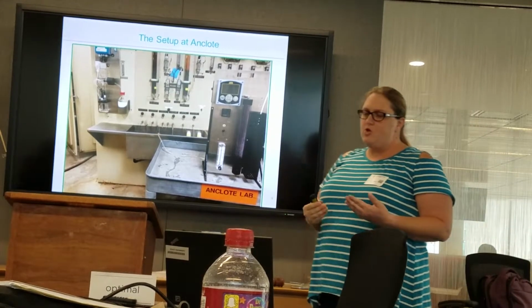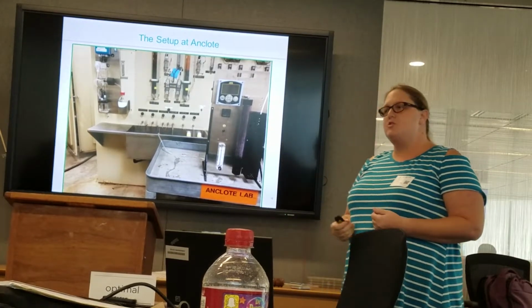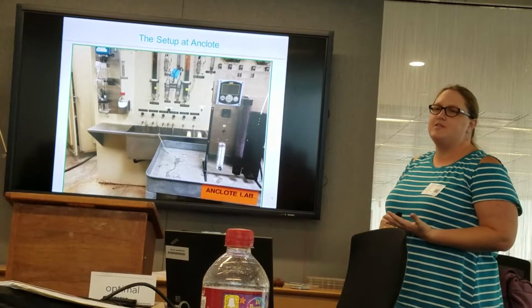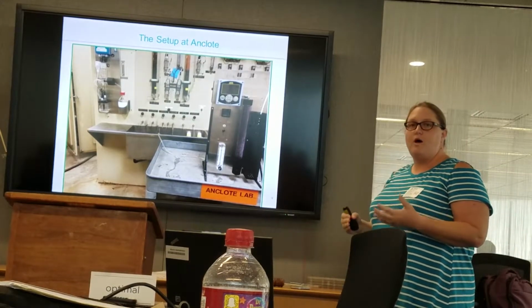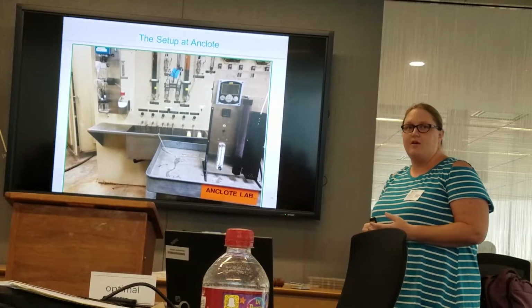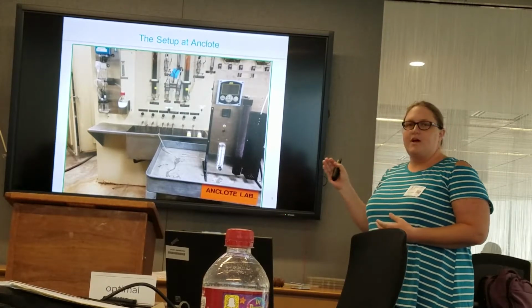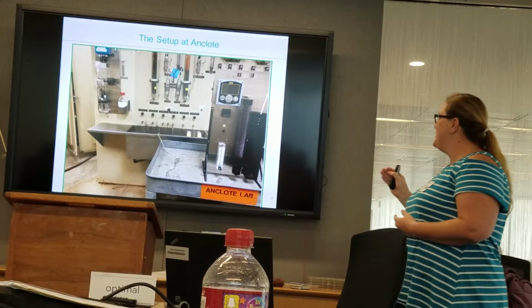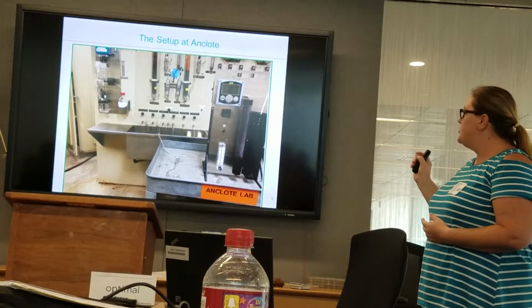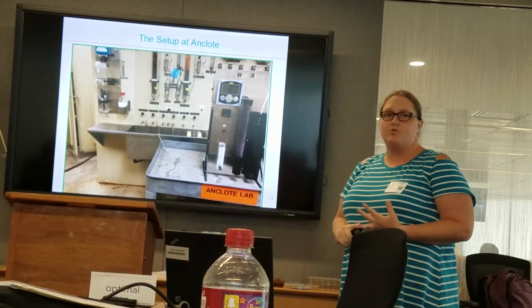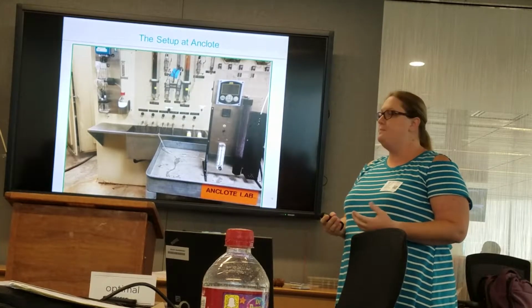So the way Anclote used this instrument, they would connect it to a sample point and let it run for 20 minutes. This basically allowed the sample to boil up to our 95-degree Fahrenheit requirement. That would take the carbon dioxide out of the system. Also, we wouldn't turn on the analyzer until we had flow and our columns were filled, to protect the instrument.